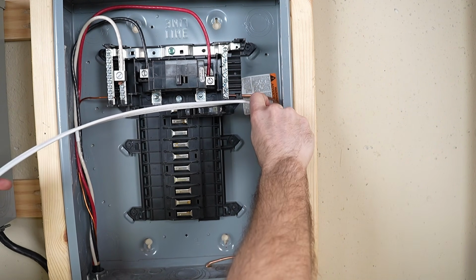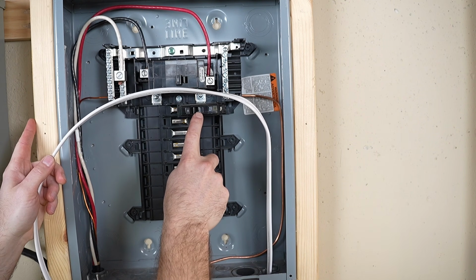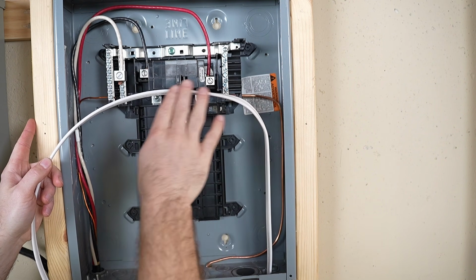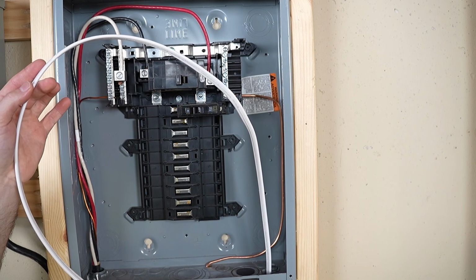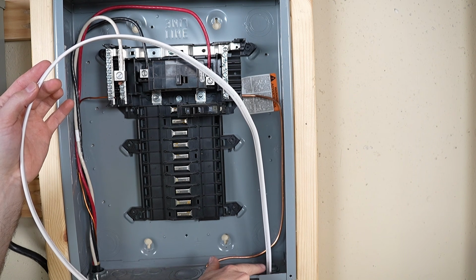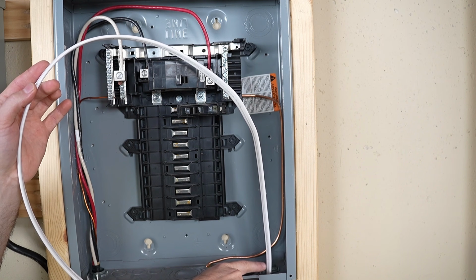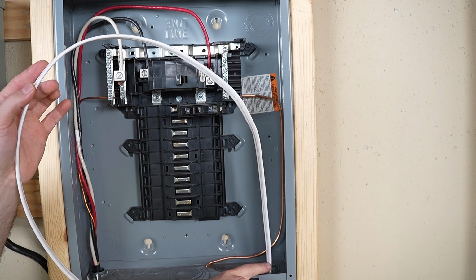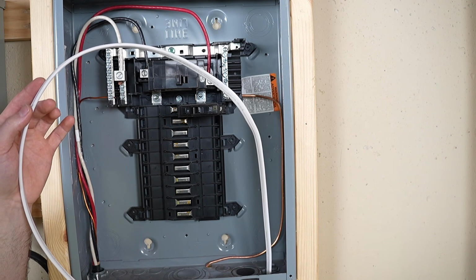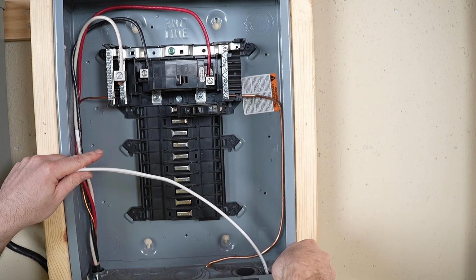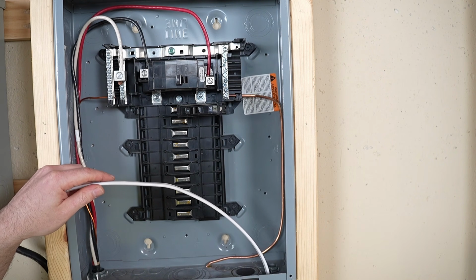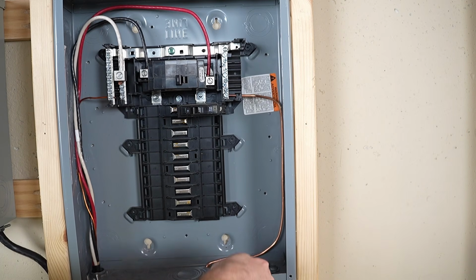So we're gonna actually bring our wire to this circuit breaker, but we've got 3 wires in here. First thing we're gonna do before we get ahead of ourselves is strip out our cable. Again, we want about 1/4 to 1/2 of an inch of insulation within the panel, and then we're gonna strip out the rest. Being careful not to cut the insulation on the wires that are within the cable.